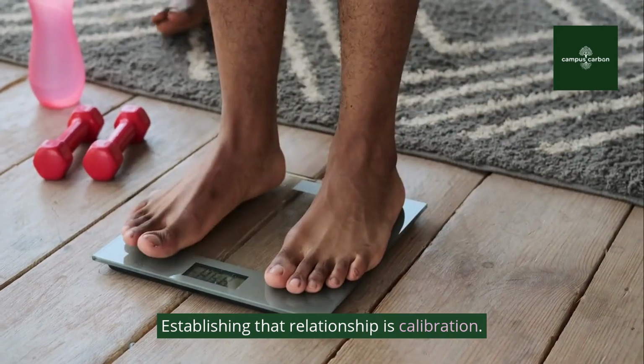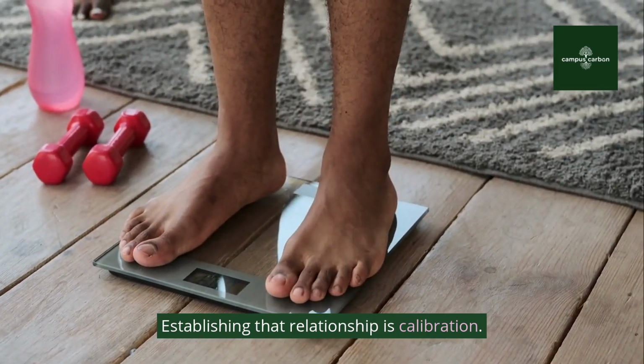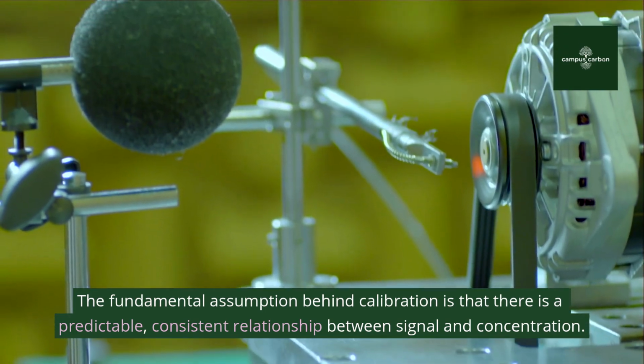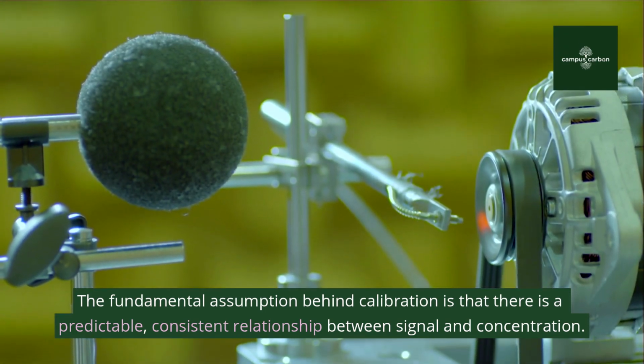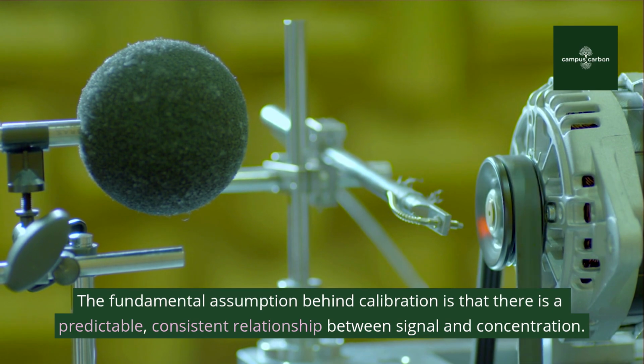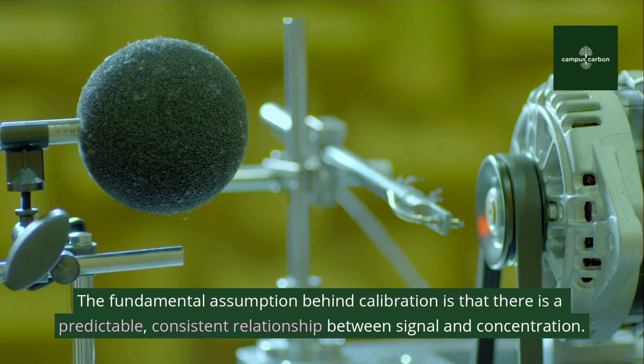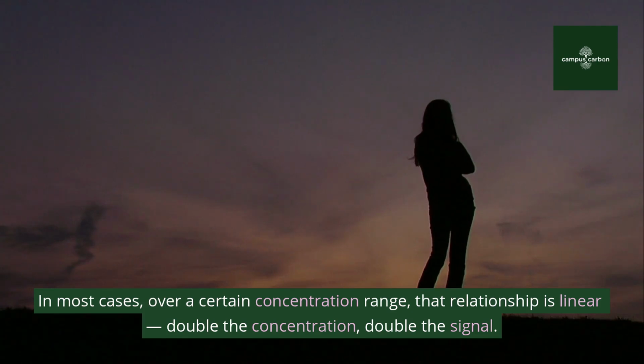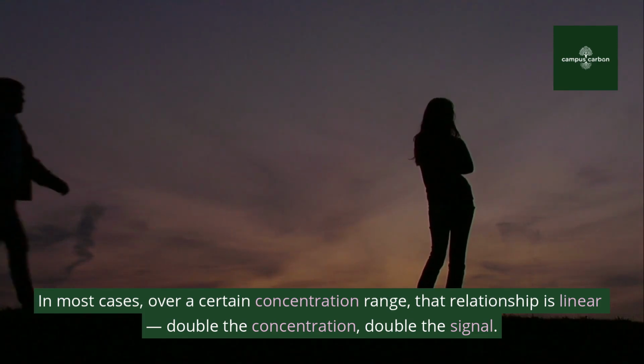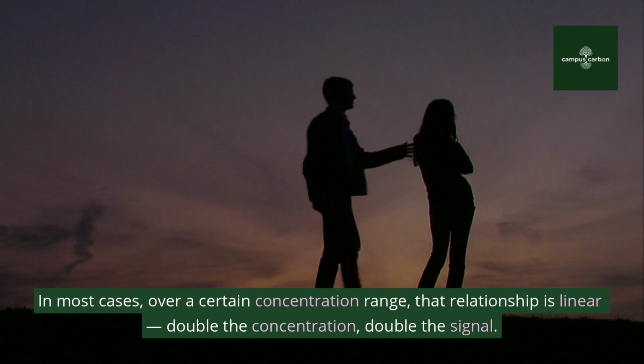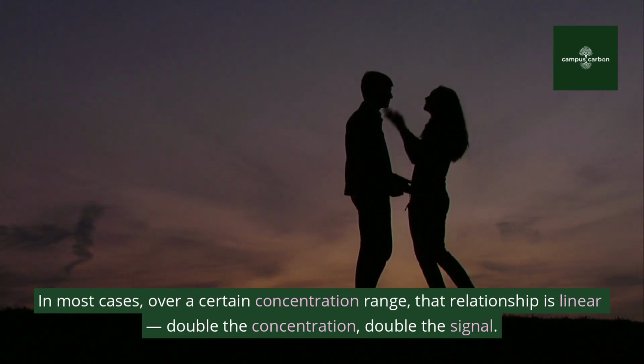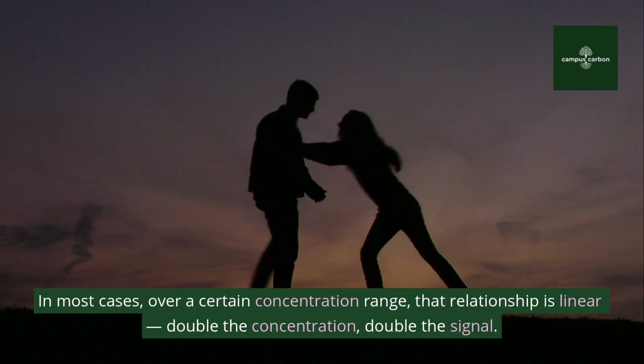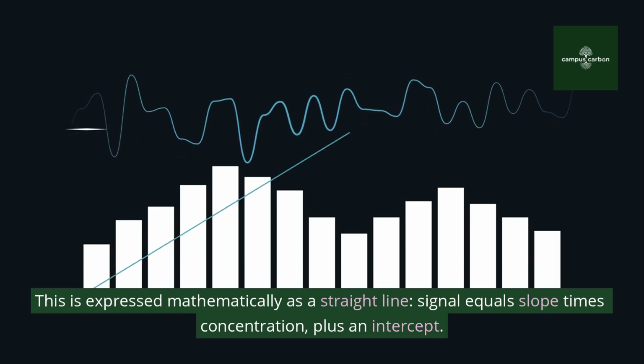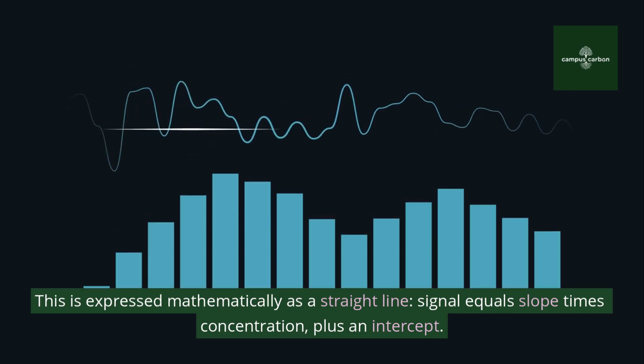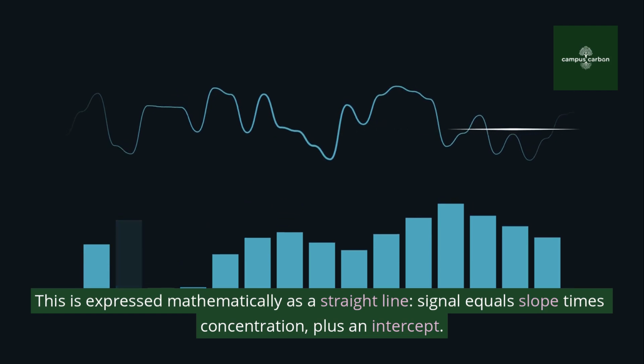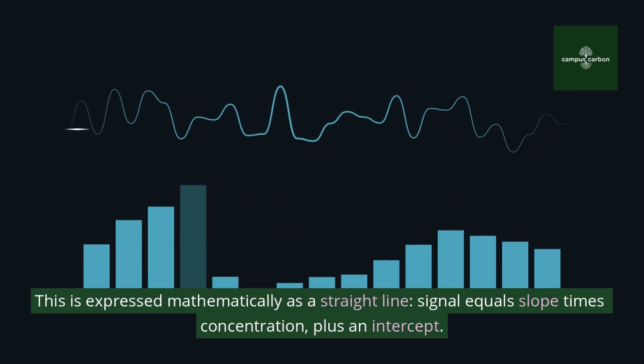Establishing that relationship is calibration. The fundamental assumption behind calibration is that there is a predictable, consistent relationship between signal and concentration. In most cases, over a certain concentration range, that relationship is linear: double the concentration, double the signal. This is expressed mathematically as a straight line. Signal equals slope times concentration, plus an intercept.